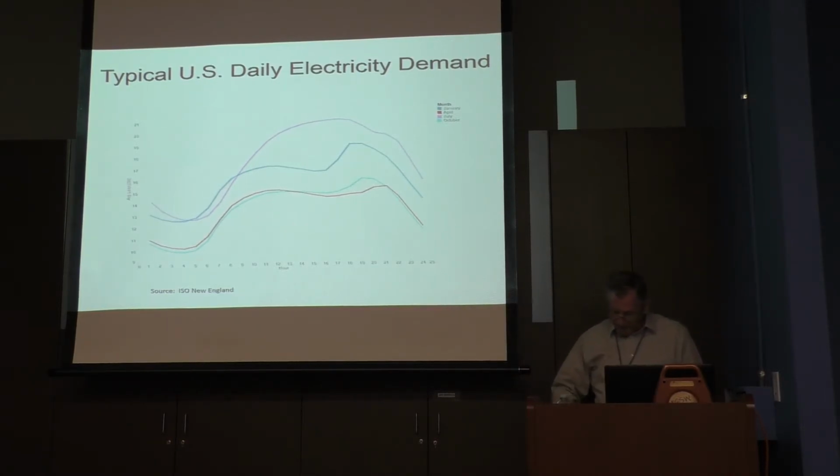Okay? And the energy demand on the grid varies not only by the time of day, but also the day of the week, the temperature, the latitude, the location, and the seasons, as well as a number of other factors. The morning ramp-up begins at about 6 a.m., and the demand returns to baseload level at about midnight. The extended summer peak electrical demand at about 20,500 megawatts, as shown in this particular graphic, occurs from about noon to 7 p.m.